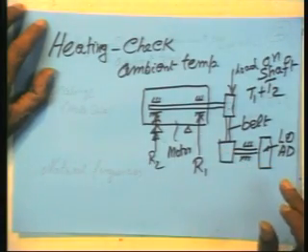You have to work out the life rate at which you are working, basing it on some average speed. You have to work out what will be the life of the bearing. Most motor manufacturers will give you this data, but many a time the normal catalogs do not contain it. You may have to go back to the manufacturer and ask about this.